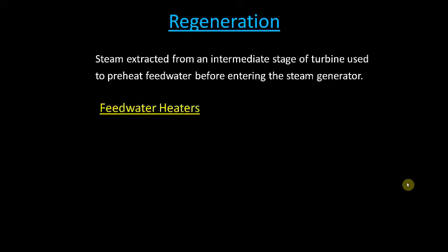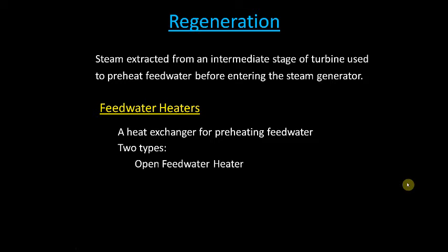So there are two types of feed water heaters that will allow us to do this regeneration. Those feed water heaters are needed because they're the exchangers that preheat that feed water. So the first type we have is an open feed water heater, and the other type is a closed feed water heater. And we're going to go into some detail about both of these.